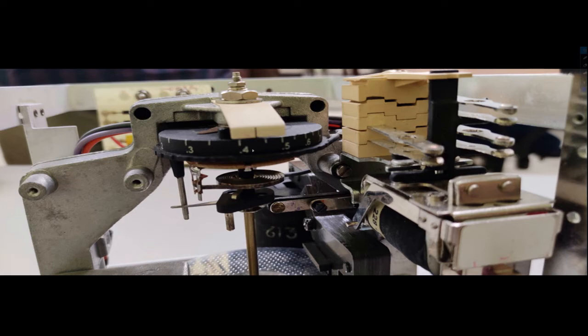Now, if we move it in the anti-clockwise direction, to 0.2, 0.3, then you see that portion comes here. As these elongated parts come here, this portion comes very close to that one, so the travel time is very low. As the travel time is very low, the relay will operate with a lower operating time. And if we move it in the clockwise direction, then this portion goes to that position, and it needs to travel a lot to close that particular switch. So in this way, just by changing the initial position from where the disk starts moving, we can control the relay operating time.